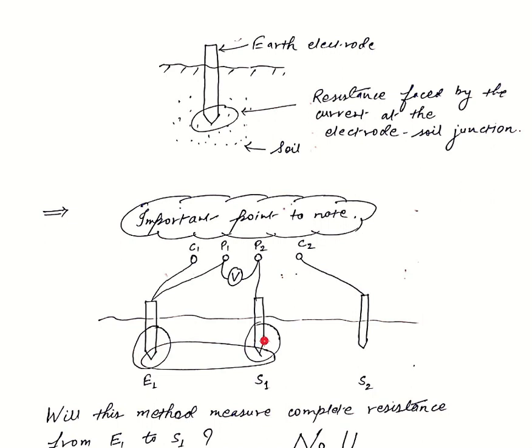But current will be flowing from this electrode to this electrode, so this resistance has been accounted for. But this resistance is not included in our measurement. Hence, we are interested only in this resistance, and this spike method measures only this resistance, that is earth resistance, and it serves our purpose.